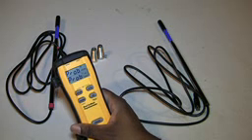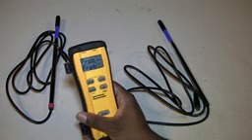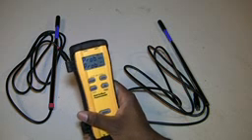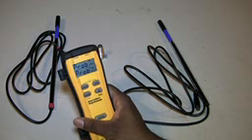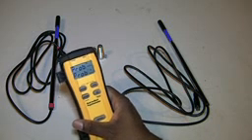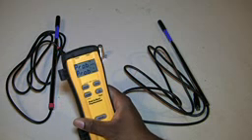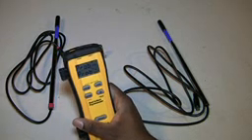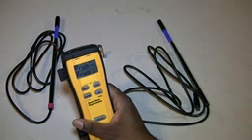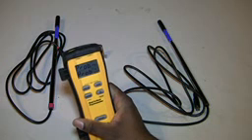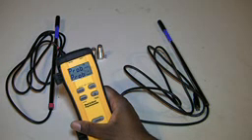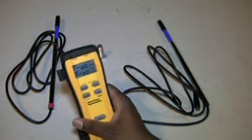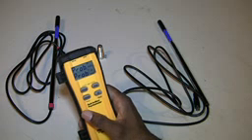For the most part I was getting close to 50% humidity, and that's after I set my humidistat to 60% humidity on the return. Now in the supply, which maybe someone out there can answer for me, in the supply when the heat was off I was getting 50% humidity. The humidity in the supply was a little bit lower than the humidity in return, understandably.